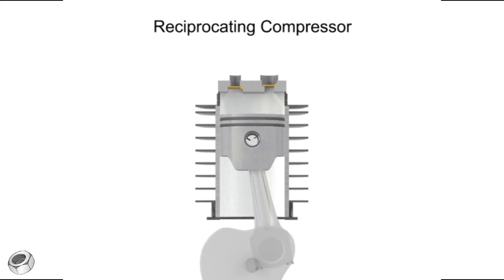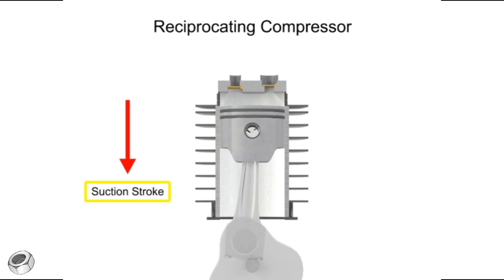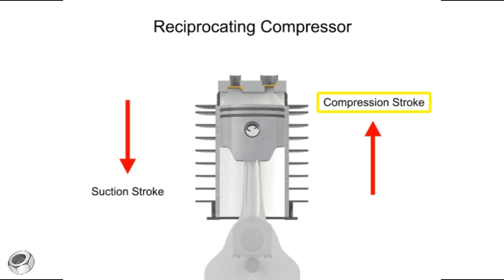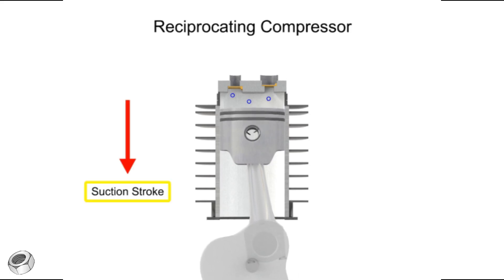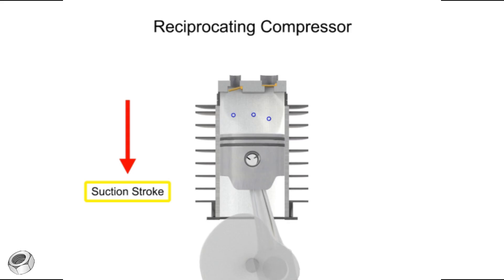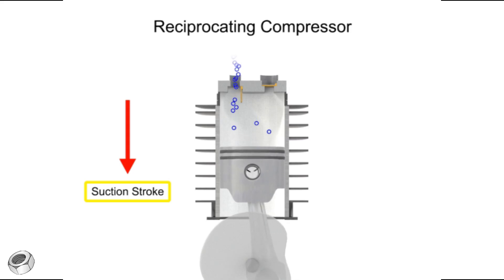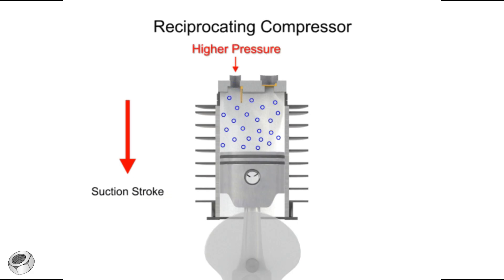The downward stroke of the piston is called the suction stroke. The upward stroke is called the compression stroke. As the piston moves downward on its suction stroke, the volume increases within the cylinder. As the volume increases, the pressure within the cylinder becomes lower than the inlet air pressure, allowing the higher pressure outside air to push open the inlet valve and allow more air into the cylinder.